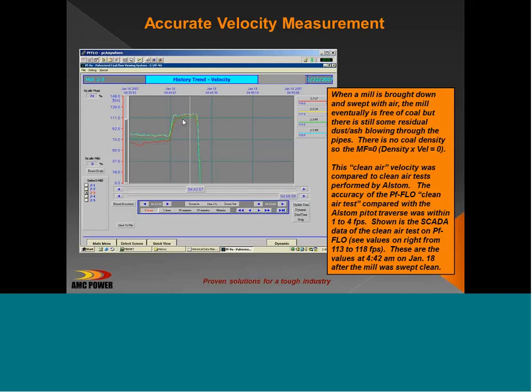The other reason I like to show this screen is that while we were doing this particular project, the reason they shut the feeder off is somebody wanted to do a clean air test. So the Pitot tube test was done in each of the coal pipes with the feeder off, and our air velocities were within 1 to 4 feet per second of the measured clean air test.